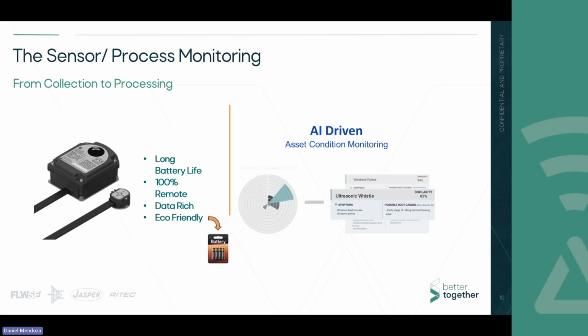Every frequency looks different. When you see changes in your frequency, you're able to deploy some symptoms and root cause analysis to tell you what's happening. In this example, we had ultrasonic pulses and ultrasonic level increases, with a possible root cause for a maintenance tech being early-stage rolling element bearing wear. So they know exactly what they're doing when they go out there—this is the first thing I'm going to check.